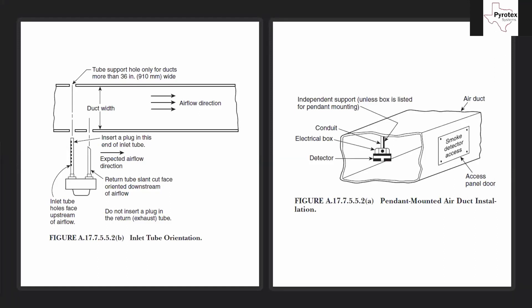On this slide, the picture on the right shows rigid mounting — there's a pendant coming down with conduit serving the wire, with the detector mounted so it samples air passing through the duct. Notice on the side they had to cut out a space and install an access door labeled 'smoke detector access.' That access door is actually code required — if you have a detector mounted inside the duct somewhere not otherwise accessible, you must provide an access door.